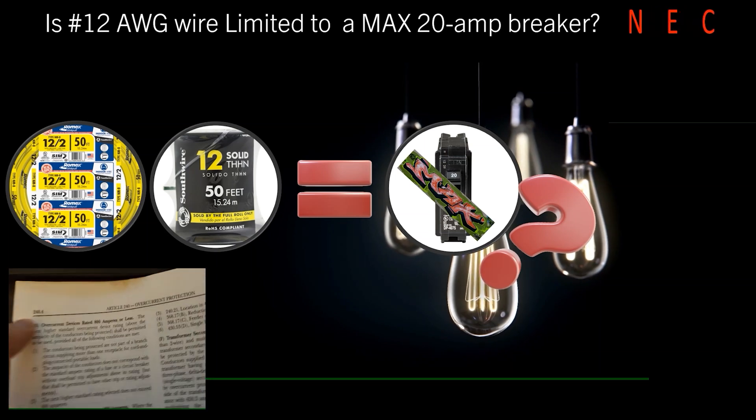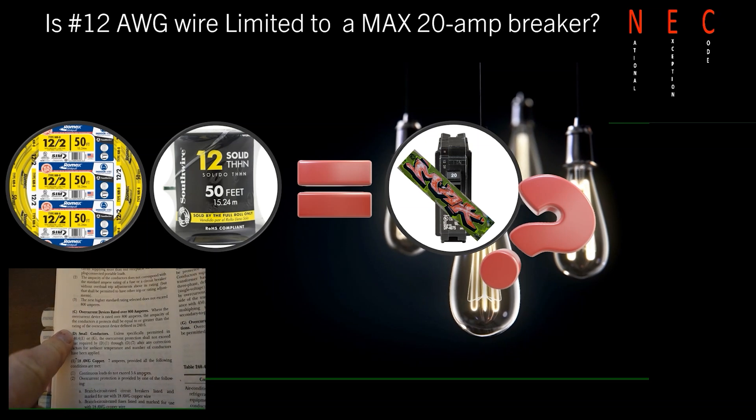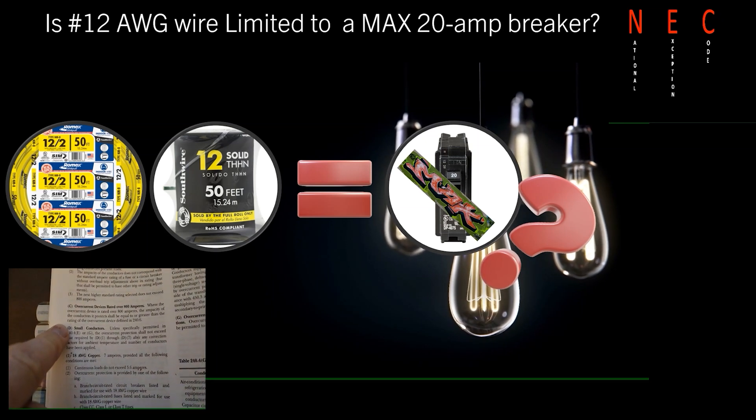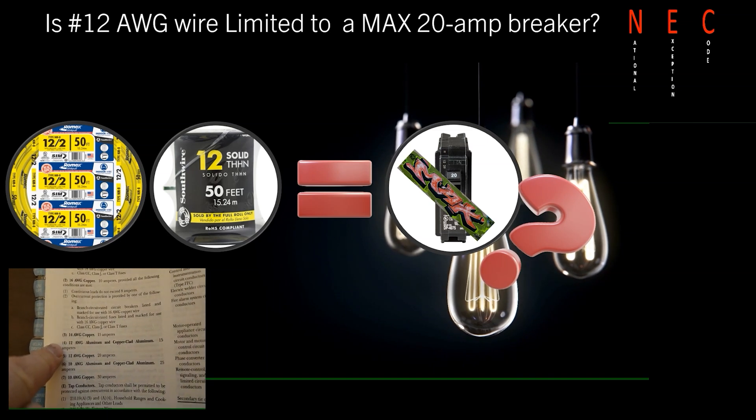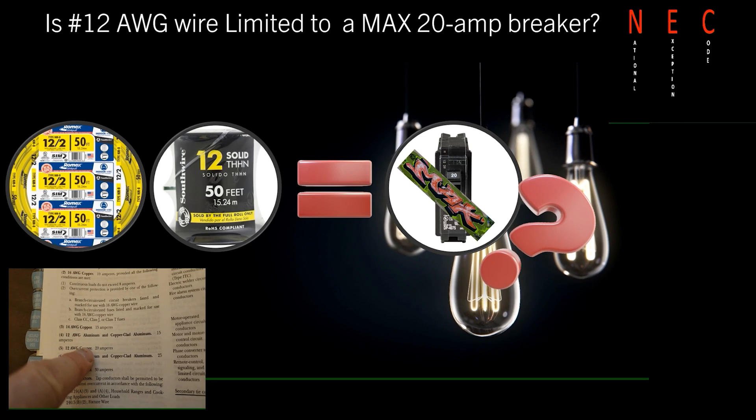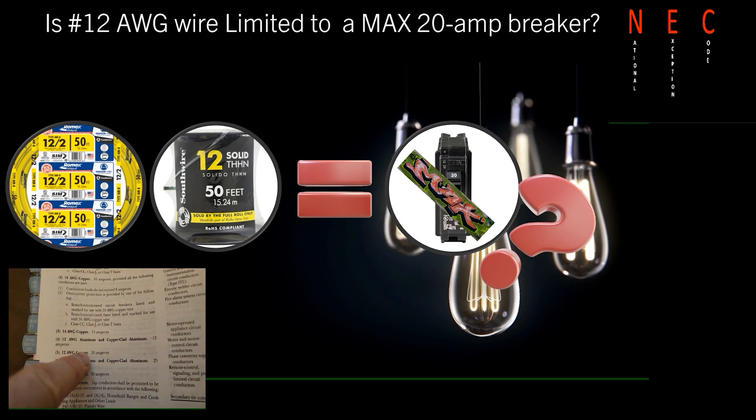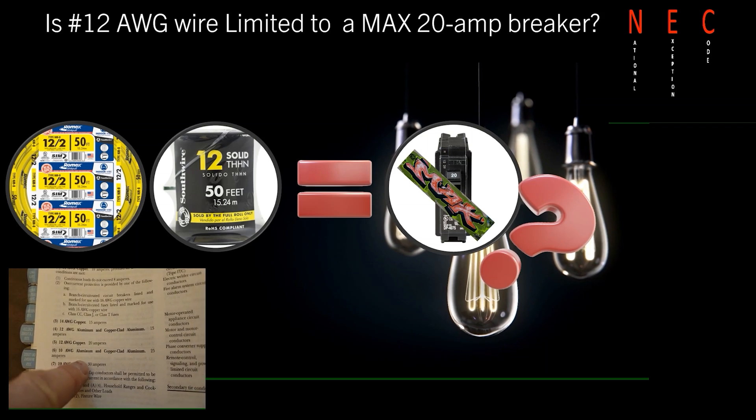But as we know, this is the National Exception Code, NEC. What this is saying is there are some exceptions that you are allowed to raise it above 20 amps on 12 gauge wire. But a blanket statement, a normal installation, yes, 12 gauge wire is limited to a maximum of a 20 amp breaker. But let's look at some of the times where it's not.